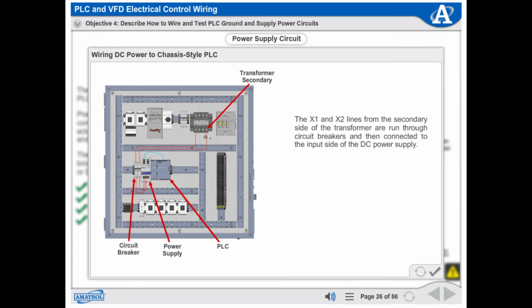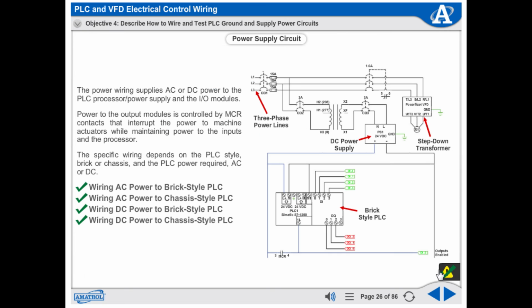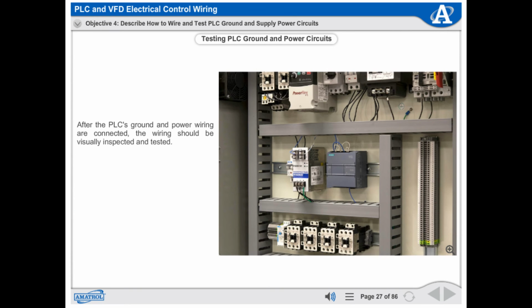The X1 and X2 lines from the secondary side of the transformer are run through circuit breakers and then connected to the input side of the DC power supply. The DC power supply output is wired to the 24-volt DC terminals on the PLC power module. After the PLC's ground and power wiring are connected, the wiring should be visually inspected and tested.